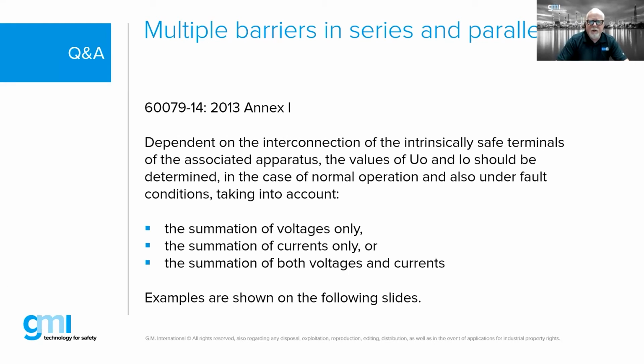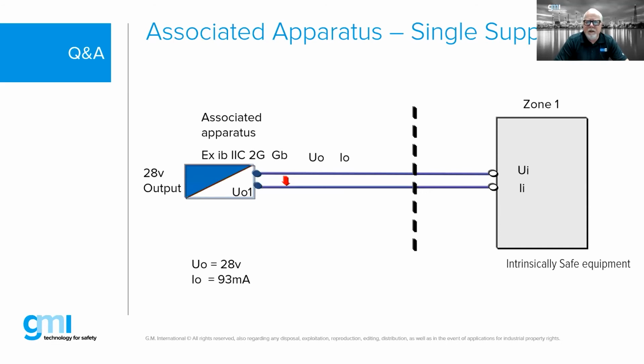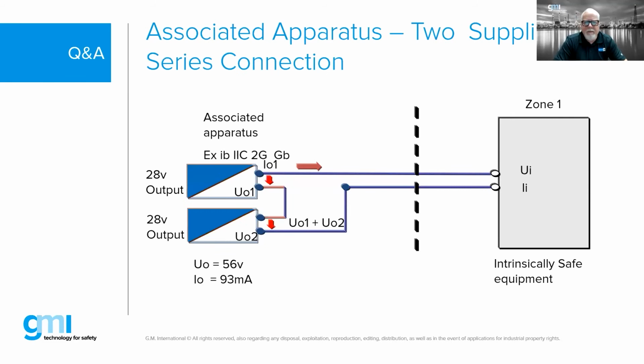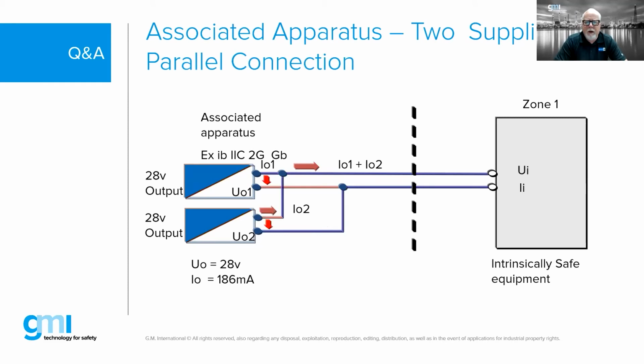On some of the other slides here, this is a single supply associated apparatus, so we have our associated apparatus with an output of 28 volts, for example, in a series connection with two supplies. Sometimes you'll find a multi-channel barrier in which you're using the output from two different outputs to increase the amount of voltage or current, to make sure you're able to operate the end device.